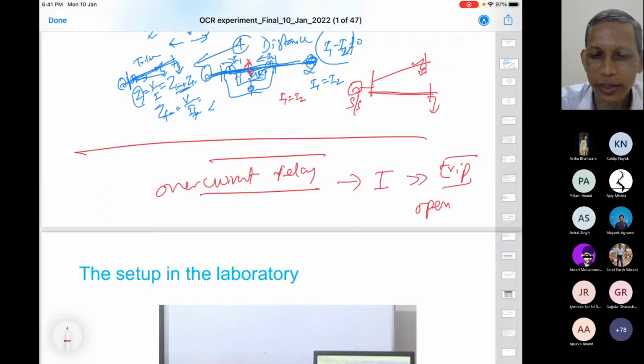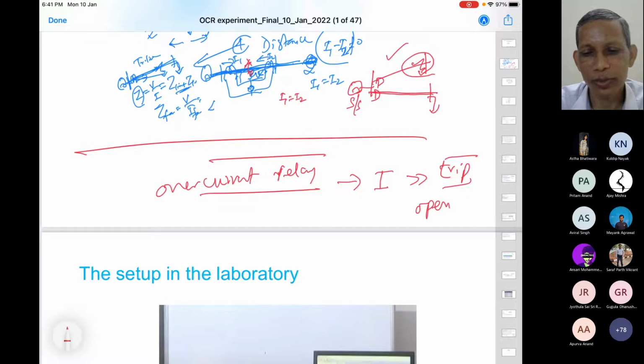So it means that our relay and breaker arrangement, the protection arrangement, should be such that whichever part is faulted, that faulted segment, that faulted line, should be the only one isolated, so that other customers are not affected. Is it okay? So this is called selectivity.